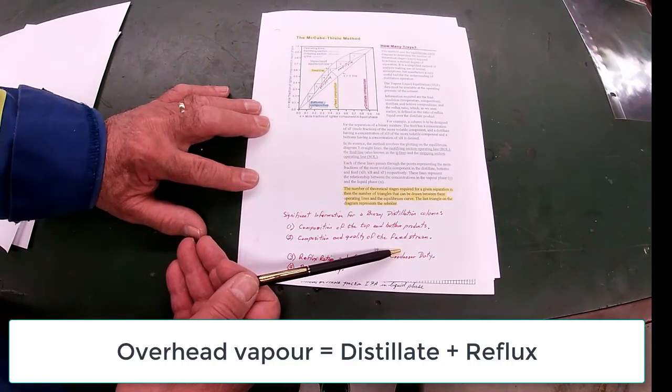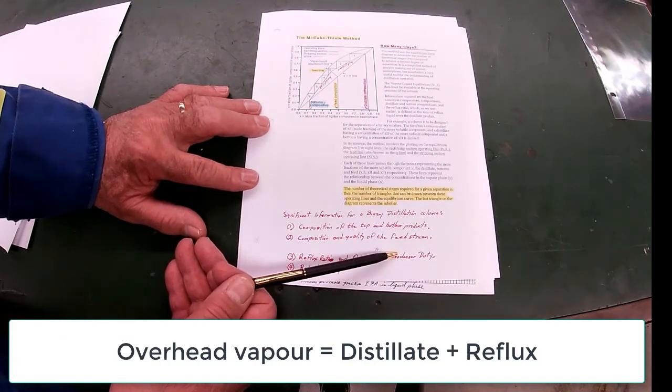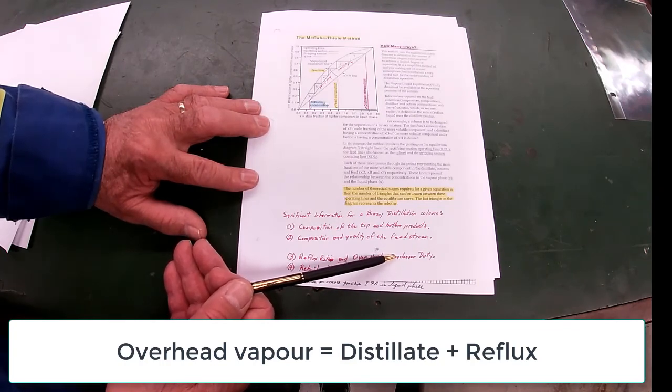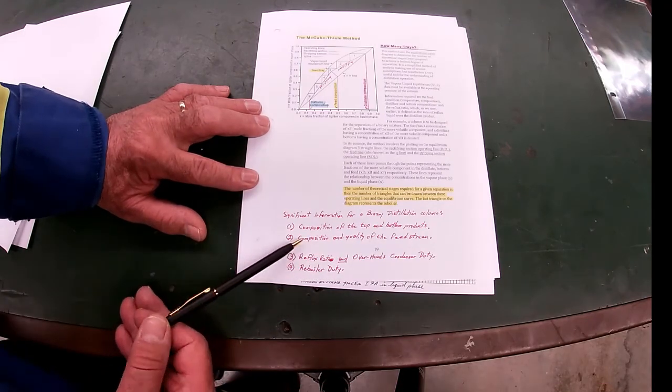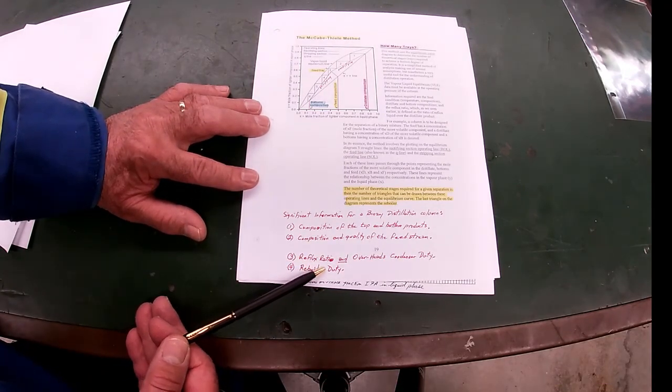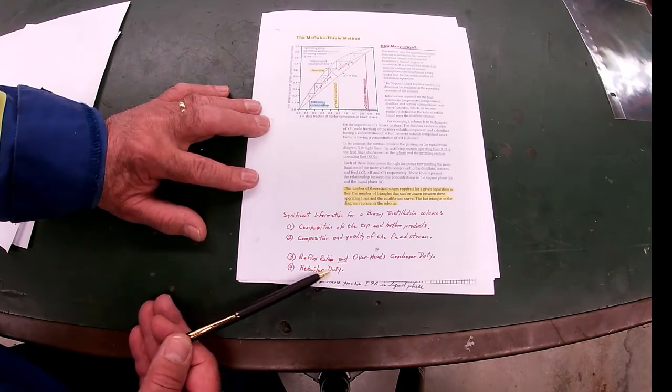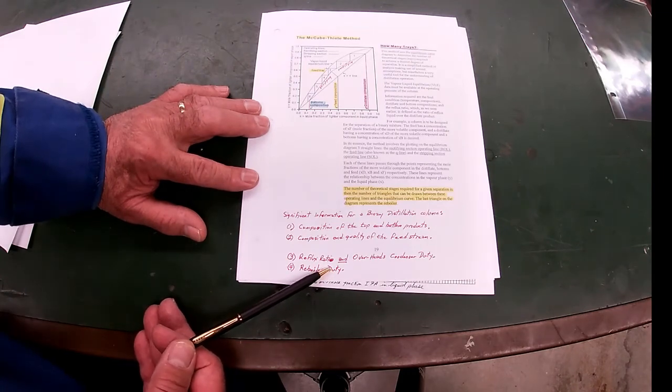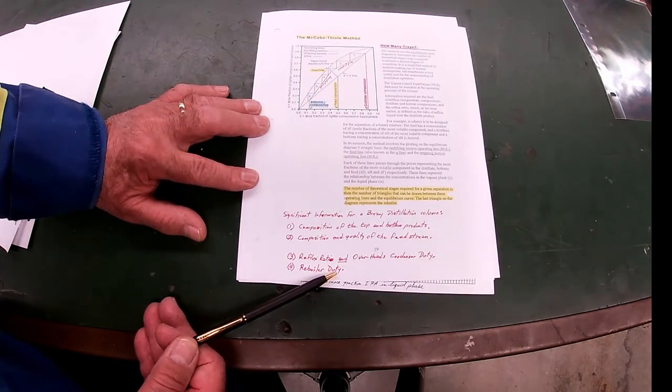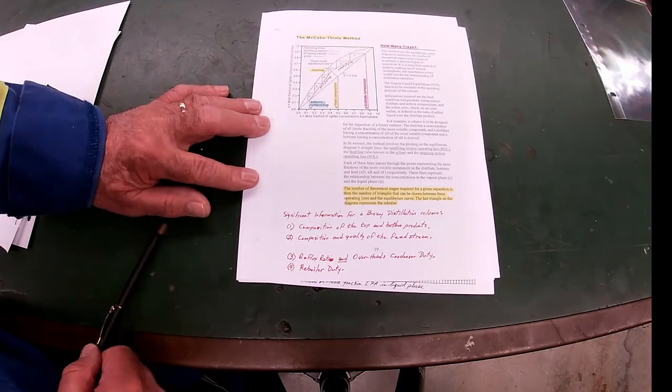Now, this is the condenser that takes the vapors coming out of the top of the tower and condenses them. And so you've got a lot of energy because you're taking out the latent heat of evaporation out of the actual vapor, I'm sorry, to bring that into a liquid phase. And lastly, we need to know how much steam we need to apply, and we call that the reboiler duty. So we need to size flow meters and control valves and other things to provide the amount of heat that we need to complete this distillation.